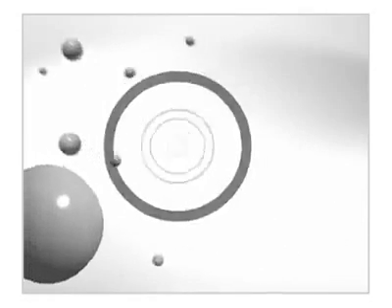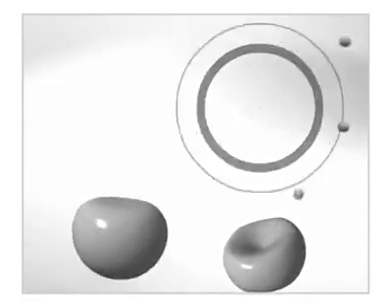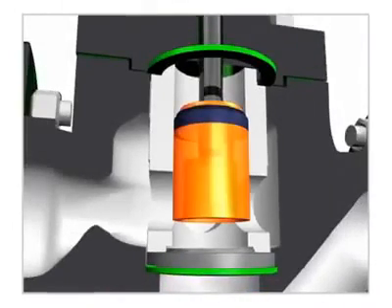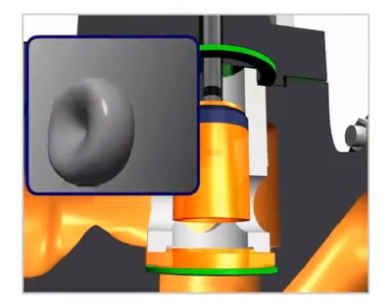These implosions can also cause local pressure waves of up to 100,000 pounds per square inch. The combination of pressure waves and microjets can cause severe damage to the valve plug, seat, and body when they're located near the material surface.